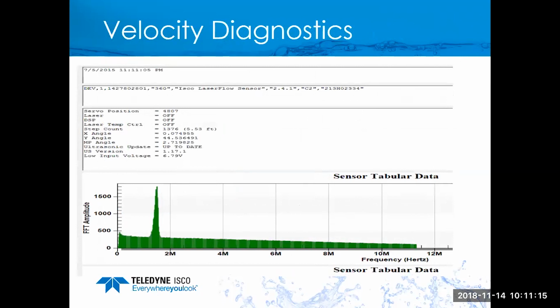All of Teledyne ISCO's flow measurement technologies have pretty extensive diagnostics capabilities. The laser is no different. The laser has a built-in accelerometer. What that does is that tells you the angle of the roll and the pitch of the sensor. But this is what we're really looking for.